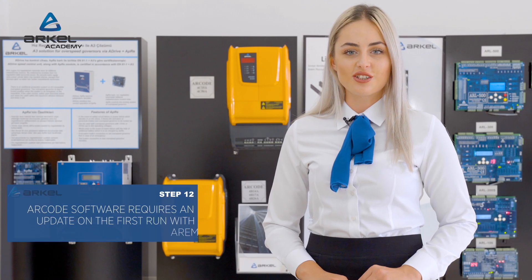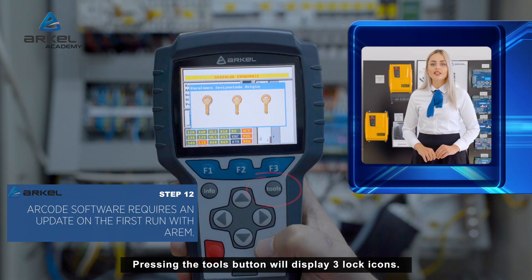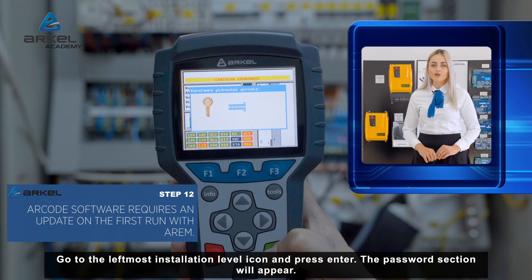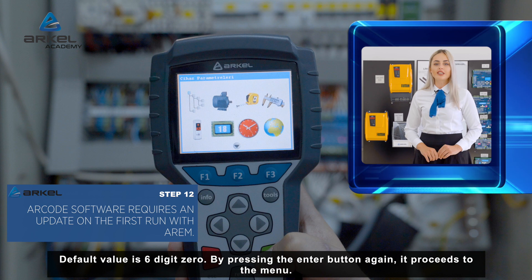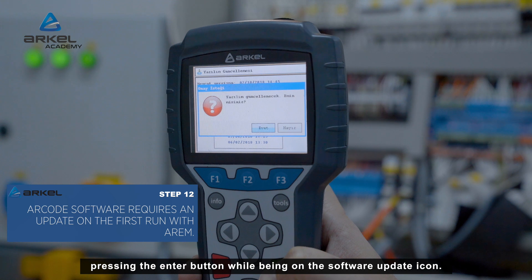The ARCODE software requires an update on the first run with AREM. Pressing the tools button will display three lock icons. Go to the leftmost installation level icon and press enter. The password section will appear; the default value is six-digit zero. By pressing enter again, it proceeds to the menu. A software update icon is available, and the software update is started by pressing the enter button while on the software update icon.